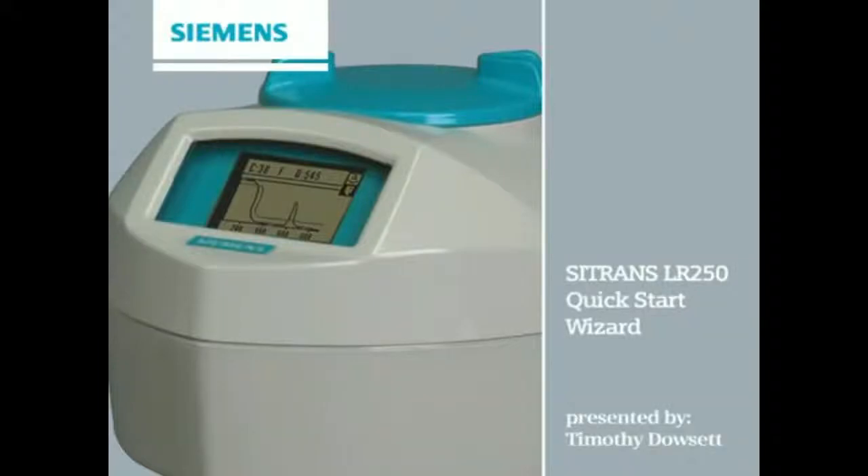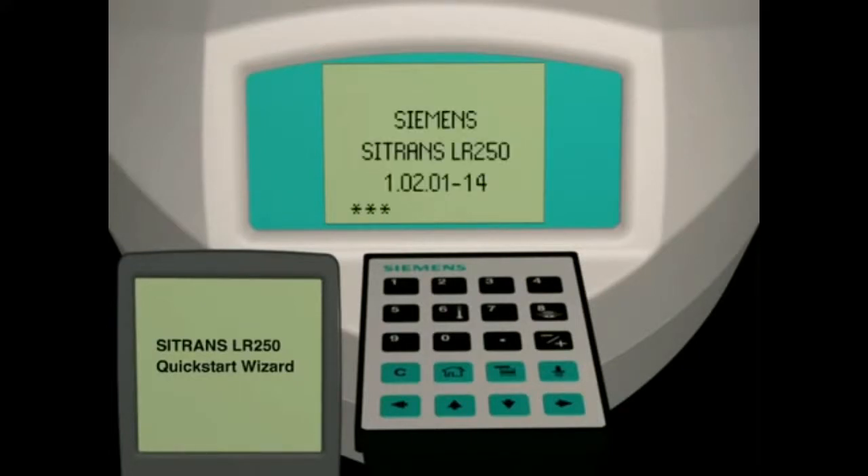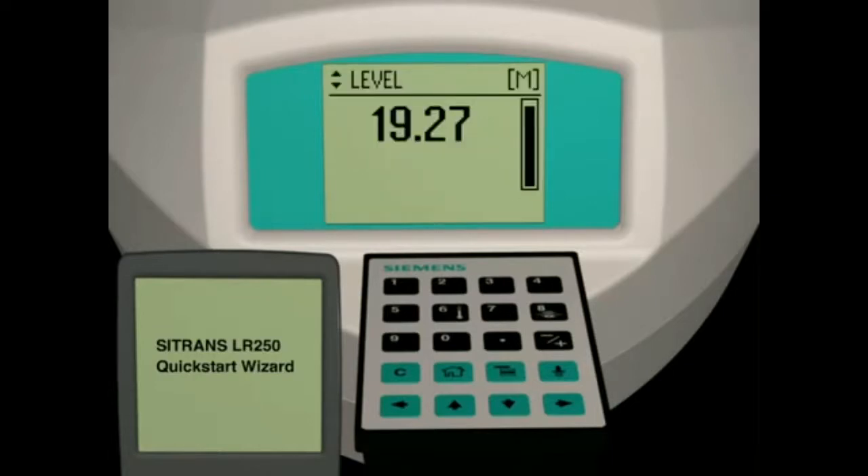This tutorial covers the LR250 HART version using the quick start wizard and a handheld programmer. When power is applied to the LR250, it performs a series of internal checks. This will take approximately 30 seconds to complete for the LR250 HART version. After setup, the unit automatically begins measuring the distance from the flange face to the material level.